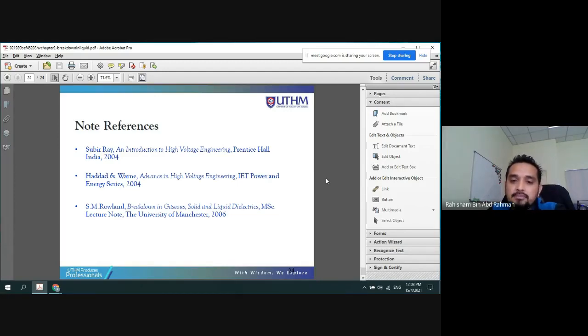In fact, we conducted an experiment in the high voltage lab using transformer oil to study the breakdown phenomena. Yes, we can see the arc, the total breakdown within the material. Once it breaks down, all the material next to the breakdown path will ionize. If we don't remove the applied voltage, this will trigger further breakdown formations, like a root that cascades between the two electrodes.